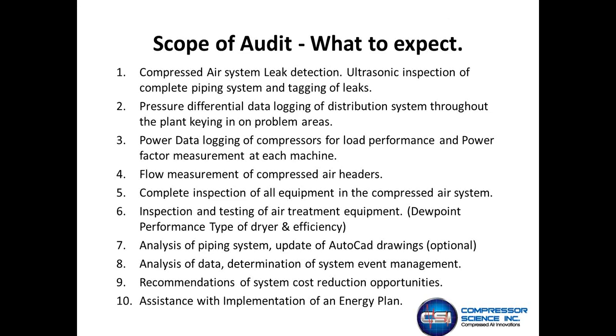So you want to take an analysis of your data, which you should accumulate: flow, pressure, amperage, kilowatt readings, and really determine what's going on in relation to the system event. There could be a dust collector going off, which we see on the flow meter as a spike. That's causing a third compressor to load up. These are all things that you need to really look at over the period of measurement of a week or 2 weeks where you're recording every second. Essentially, you should have a good understanding of what's going on with the system.